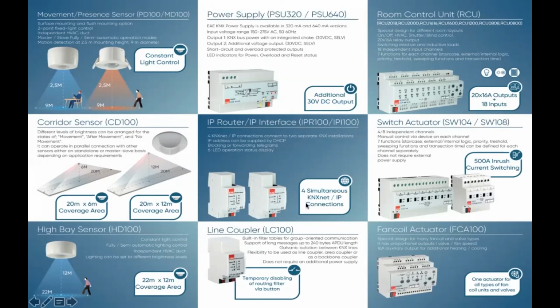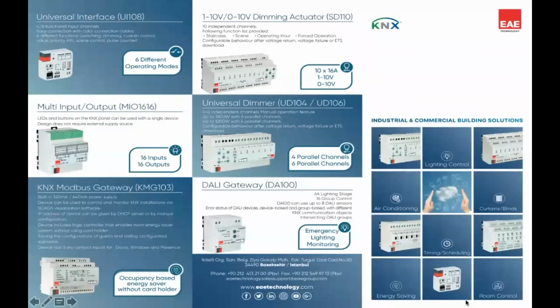All the accessories for KNX, IP router, IP interface, and line couplers are also available from our portfolio. And we have a separate fan coil actuator if you need it for controlling any fan coil unit. We have a very small binary interface, or universal interface, which can go behind any switches, and this gives you 8 inputs, and each button can be programmed to do any KNX operation. Apart from that, we have a DIN rail based 16 input 16 output module as well. This can go at rack size, and you can connect push button switches to it. We have a brilliant KNX to Modbus gateway. If a project requires integrating Modbus based devices into the KNX world, you can use this.